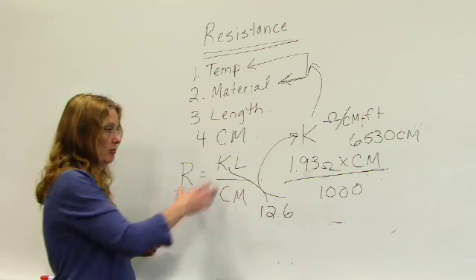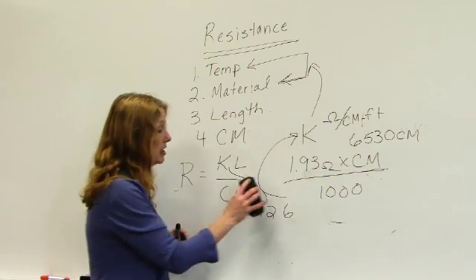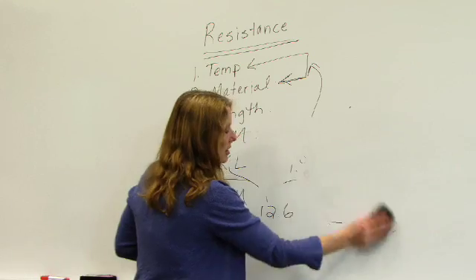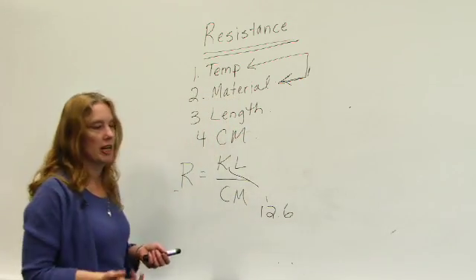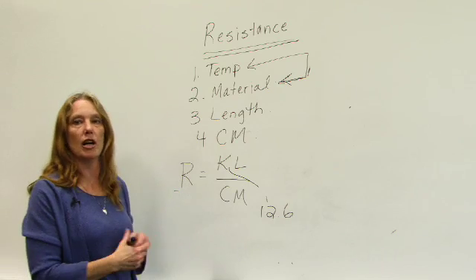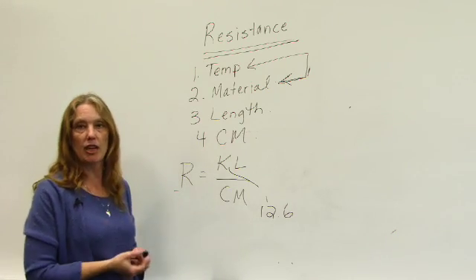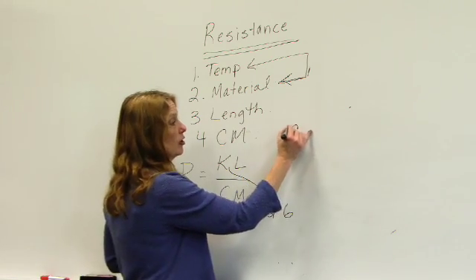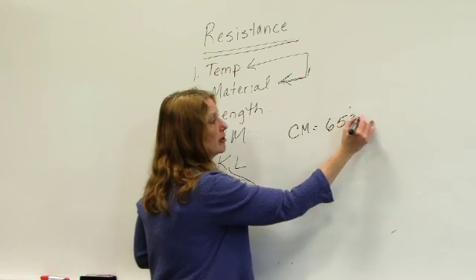So let's apply this value. Let's look at this whole circuit and say I have a wire, and I have a conductor, and we'll keep that 12.6 because we already calculated it. And I have a conductor, and that conductor is 100 feet long. So I have a 100 foot long conductor. It's a number 12 gauge copper, so we know our circular mill area. So the circular mills of this number 12 is 6530 circular mills.